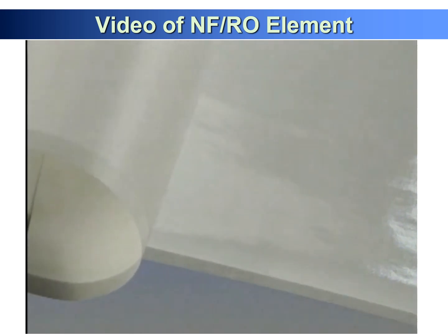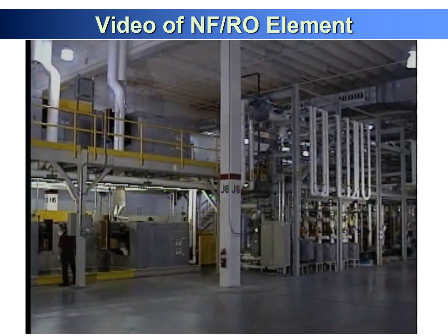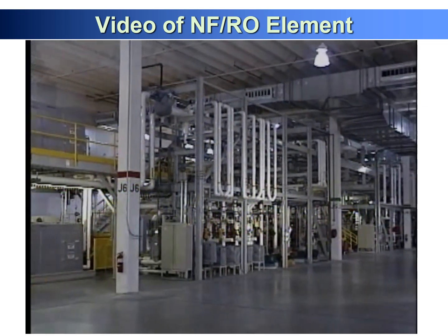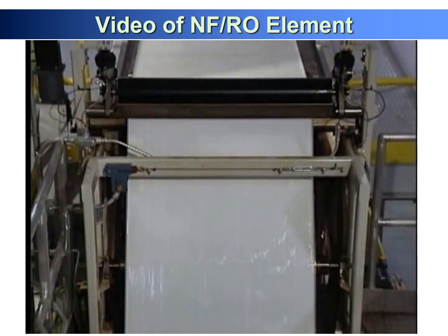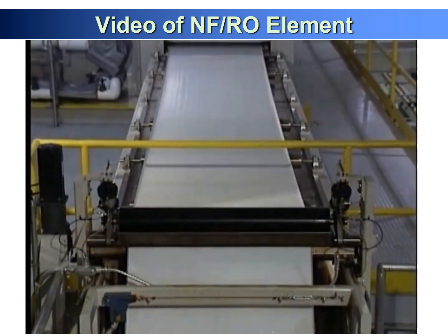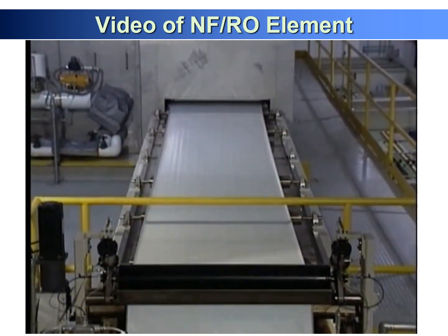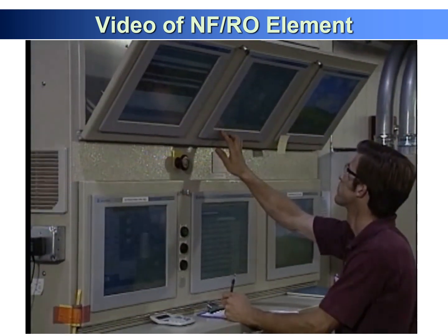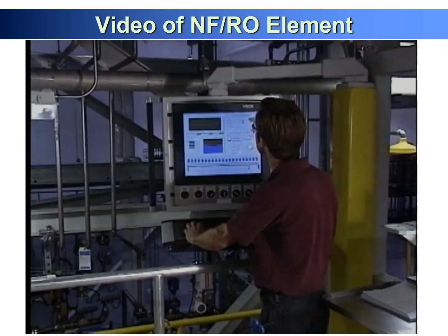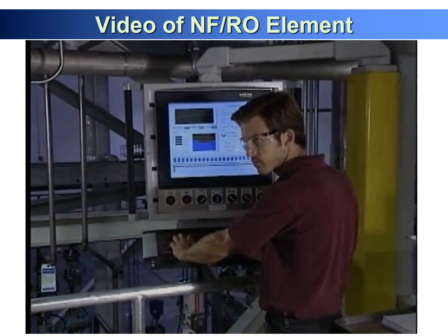FT30 thin-film composite membrane, invented by FilmTec nearly 3 decades ago, is the genesis of today's industry standard. With each new generation of manufacturing equipment, the quality of FilmTec membranes is continuously improved through advanced process automation and control, from handling polyester-based material through casting the microporous polysulfone support to the complex polymerization reaction that creates the polyamide membrane layer. Design innovations allow us to use advanced membrane recipes that improve membrane performance and consistency. Dozens of critical variables are controlled and inline quality checks are performed to produce consistent, defect-free membrane without patching, giving FilmTec membrane the widest pH cleaning range in the industry.